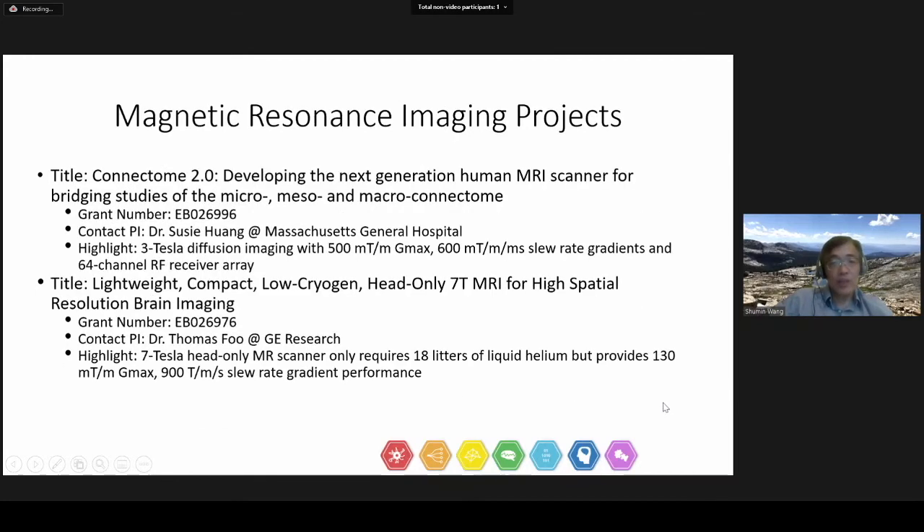In 2018, we funded other MRI projects. Dr. Susi Huang from MGH proposed to develop very strong MR gradients featuring 500 millitesla per meter peak gradient strength for 3 Tesla diffusion imaging. Dr. Thomas Fu from General Electric Research proposed to develop a 7 Tesla head-only MR scanner that only requires 18 liters of liquid helium, which is less than 1% of that required by a whole-body system.